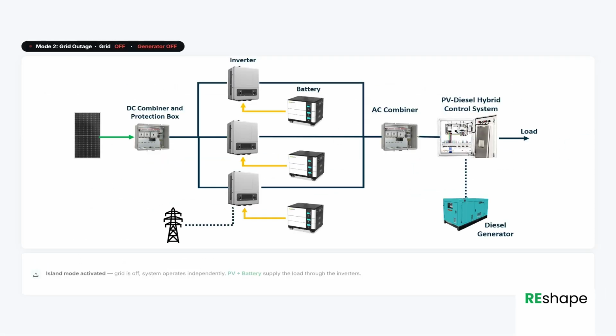In the grid outage mode, where grid is off and generator is also off, the system goes to island mode. Inverters will supply the load from the PV and battery. If PV generation is insufficient, then the battery discharges to maintain loads. If the PV generation is insufficient and also battery SOC is less than threshold, then it will switch to mode 3. The PV diesel hybrid controller will start the DG and will shift the source to DG for a seamless supply.